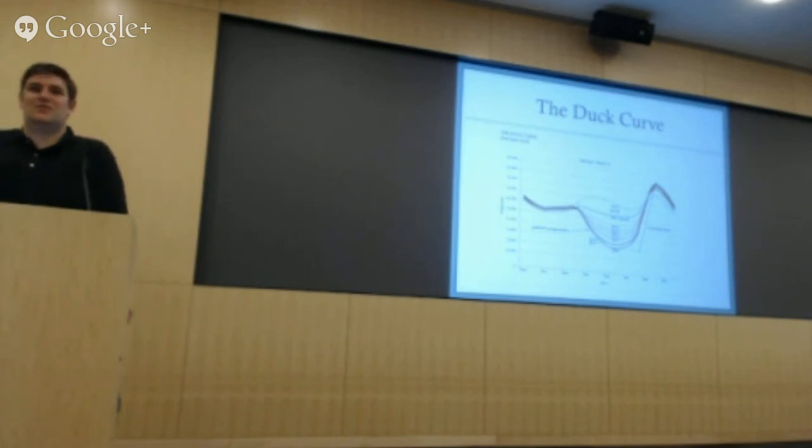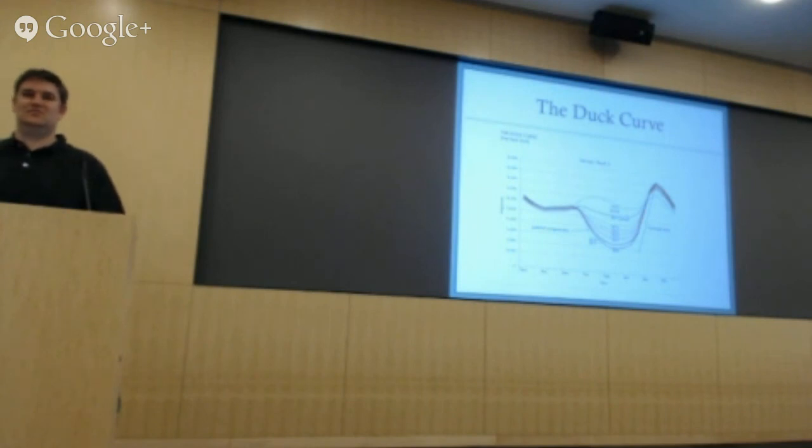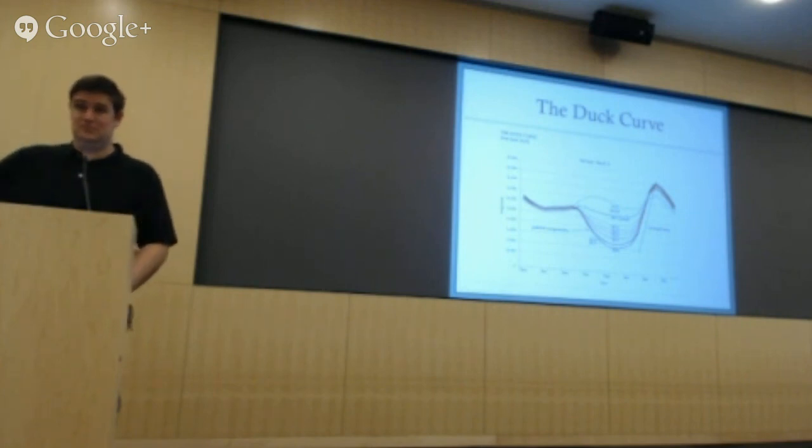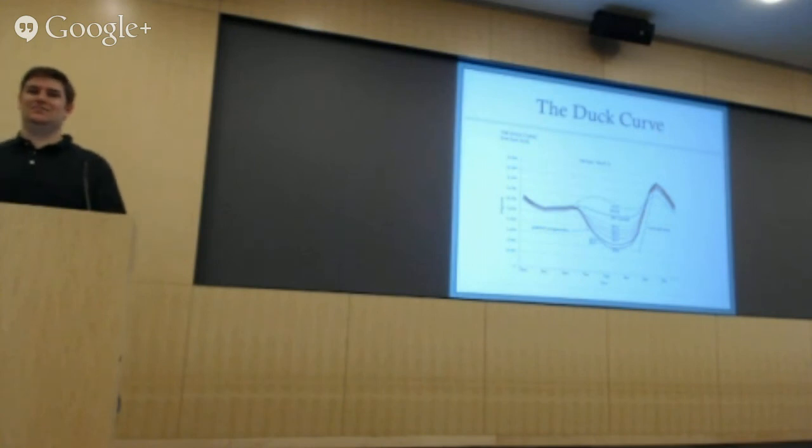Especially, you make a comment on that. The higher the difference, the less water you have to move. So your civil structure gets smaller with a higher differential height. Ideally, you'd like to take the water, pump it from the ocean to the top of Mount Everest and run it back, because you're using gravity. Yeah, using gravity. But the problem is you need two reservoirs for a pumped hydro system, and you can get away with one if the sea is the other side.